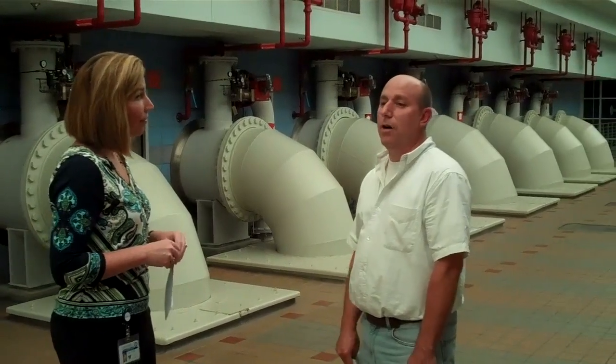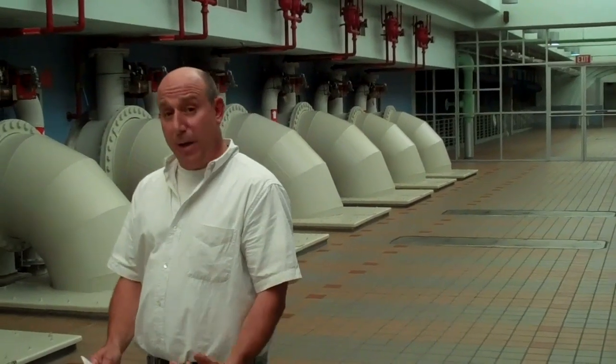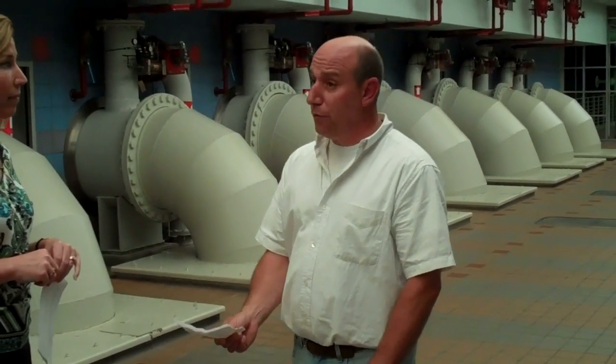In 1992, Greater Cincinnati Water Works began the process of filtering all their water with granular activated carbon. After the water has been sand filtered and the suspended particles are removed, the water is filtered through 11 feet of granular activated carbon. This carbon acts as a sponge and adsorbs organic matter that should be removed from the water to improve the process.